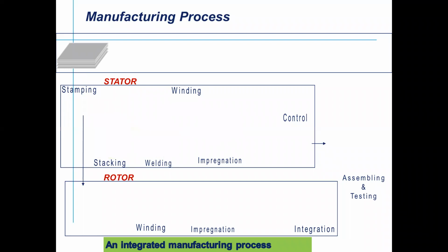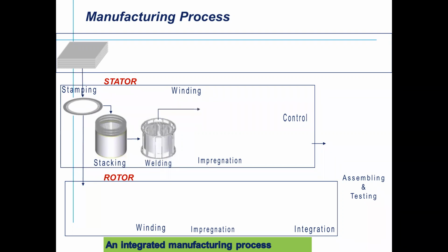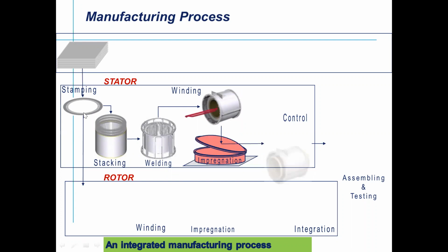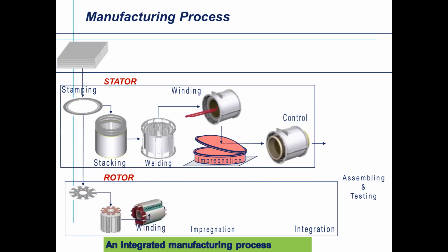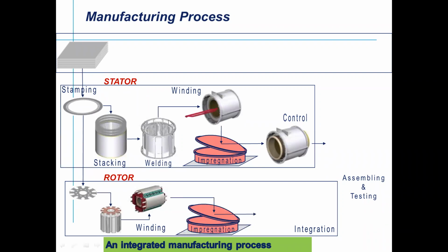Okay, fine, thank you. So coming to how the manufacturing process happens in the alternator, these are the stampings which will be used, and the stamping is made as a profile to the slot. Maybe 48 slots or 60 or 70 or 82 are required, based on the design. So this core stacking is done, and further to that, stator assembly, welding, winding, and after that impregnation.